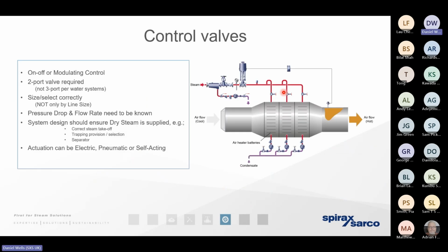Control valves are typically used for temperature sensitive processes. They can be electrically or pneumatically actuated. Common problems that we come across with control valves are they're very, very often oversized. If we've got an oversized control valve, the seat and the plug are likely to operate very, very close together. And that means if we're distributing steam, for example, at 40 meters per second, 90 miles an hour, that's the speed of the steam in the pipe. If that steam's being throttled as it moves across the control valve as a result of the seats operating very close together, that steam velocity could increase tenfold.